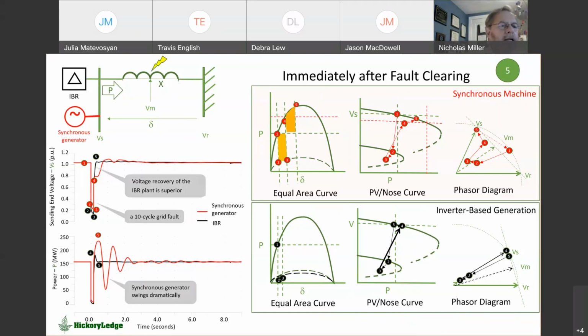All right, so into the disturbance just a little further, we reach the top of the power swing for the synchronous machine. You see the equal areas shaded in orange are equal. That's basic theory. That means that the system has dissipated the accelerating energy that it acquired during the fault, and it's going to go back. It hasn't actually quite gotten up onto the old nose curve yet because the voltage hasn't recovered. If I looked very carefully at the red voltage trace, you would see that that was a marginal voltage recovery by WECC criteria, right? Remember that post-fault voltage swing, post-clearing voltage swing can't go below 75% for a class A and B type disturbance in WECC.